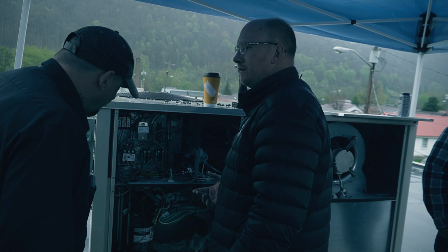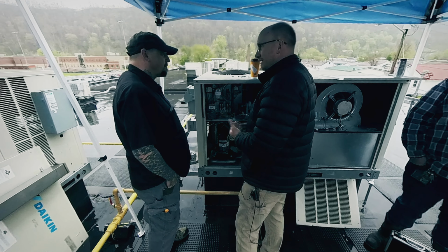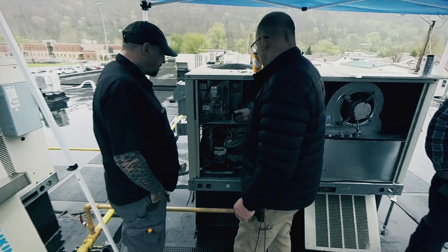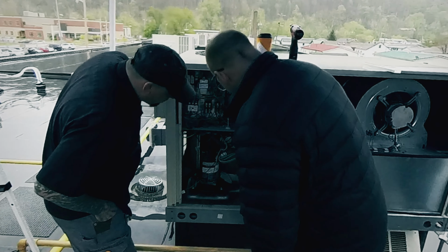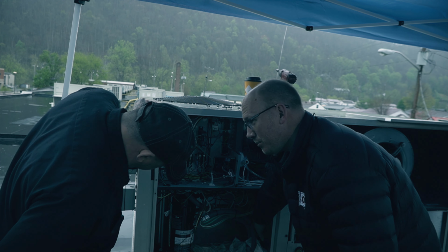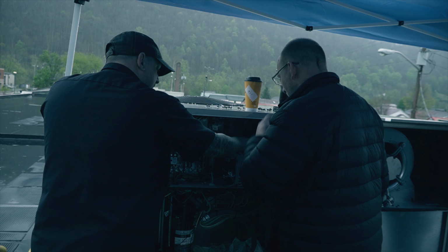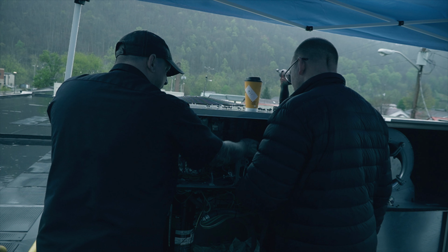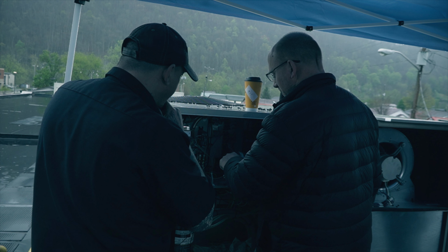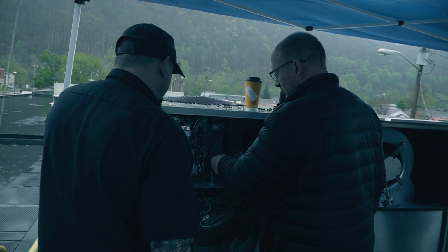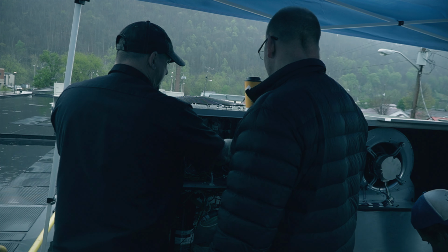If it's cold out here and you're trying to run the compressor and the fan, and the fan's not running and you need it to run, your power comes from here, goes through this, pretty much a fan cycle switch, high pressure switch, up to here. So this doesn't have anything to do with your fan either? No. If this was out, your fan would still run? Yeah, your fan is still running. This is pretty much your relay for your fan. So you just have to jump these out. It's normally open.